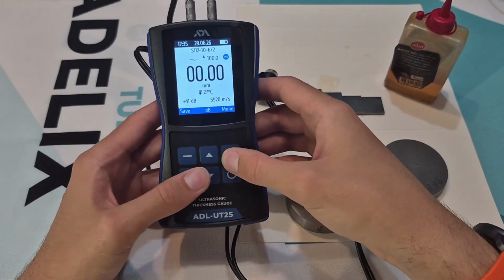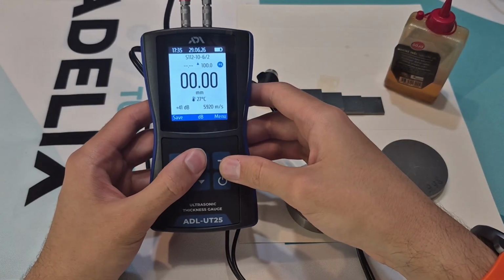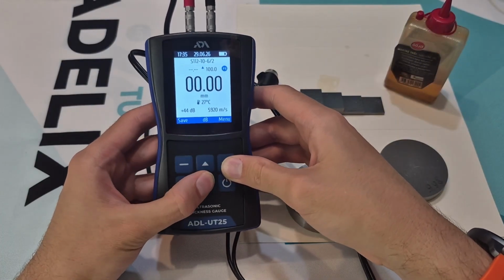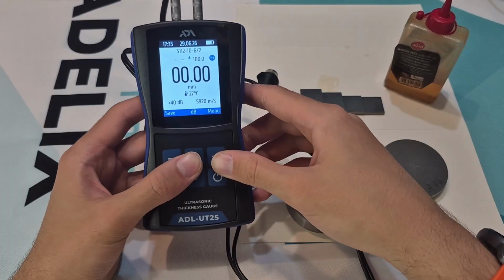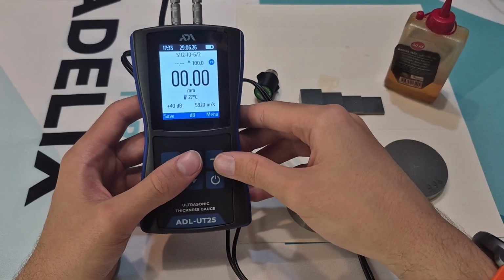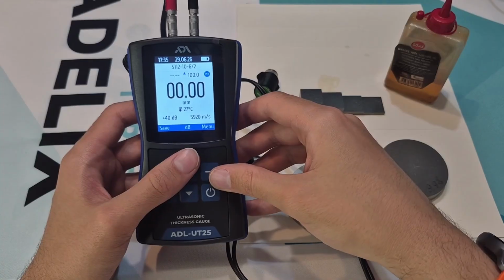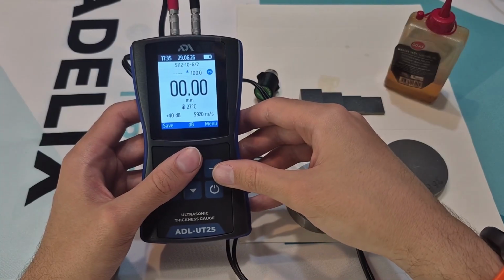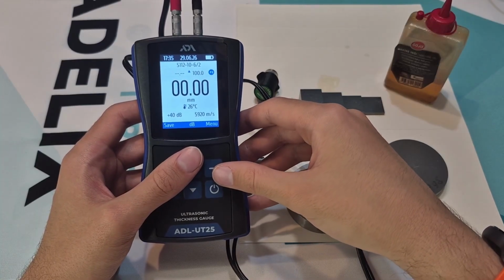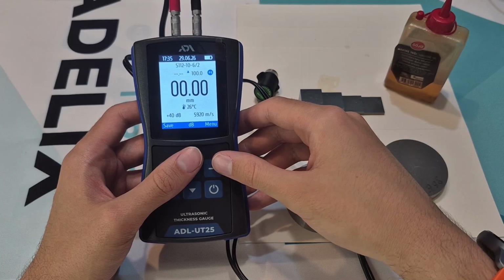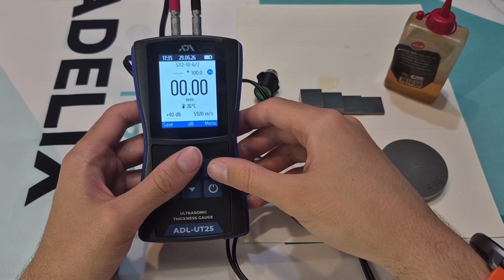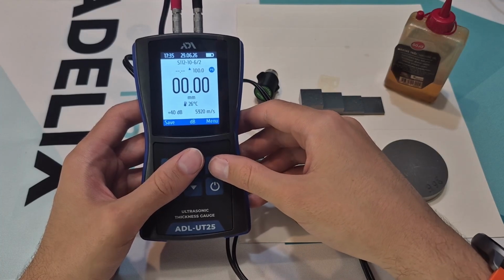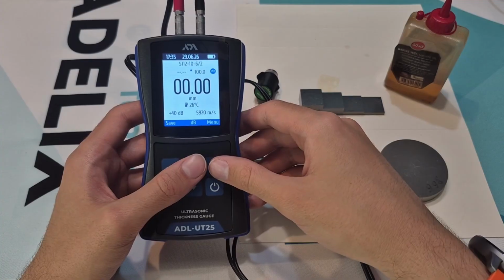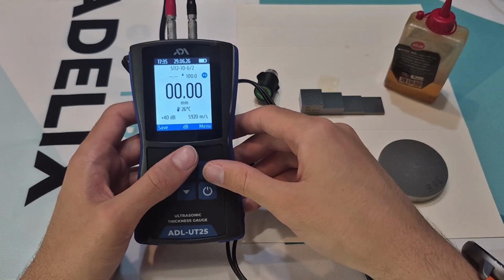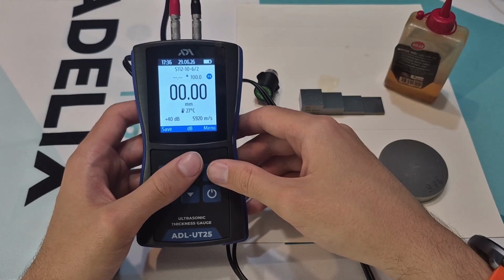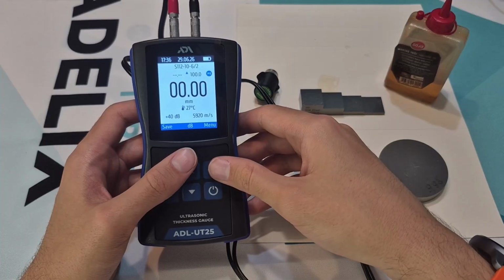The next parameter is gain. It is adjusted with the up and down buttons. Gain affects the sensitivity of the transducer. For measuring thin parts, it is recommended to reduce the gain. For thicker parts, it can be increased. After zero calibration, the gain value is set automatically, but it can be adjusted for a specific task if needed. On the right, the current ultrasonic velocity is displayed, and it can also be changed.